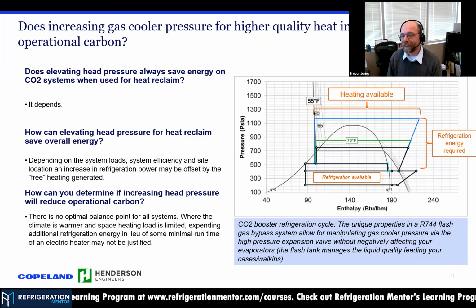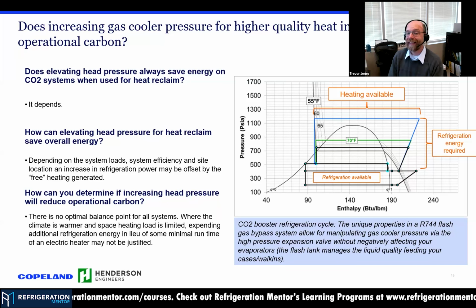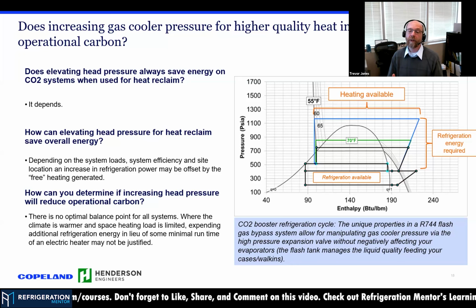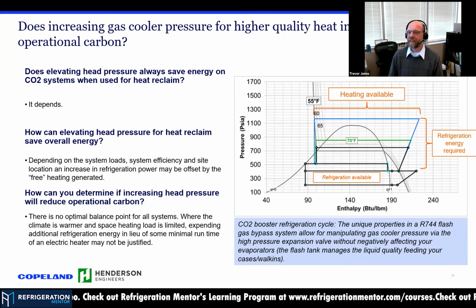So one thing we looked at was pushing the pressures on our CO2 systems above minimum to see if we could get a little more heat. That actually came back with a slightly interesting answer, and it kind of depends. One of the things is you have to be able to use all of the additional heat that the system is producing. If you don't, then you're not fully condensing. By fully condensing, you keep your mass flow for the system fairly low, because a compressor is not a great way to generate heat. It's good for moving heat, but it's really not as efficient as, say, an electric resistance heater for generating heat from electric power, if that makes sense.